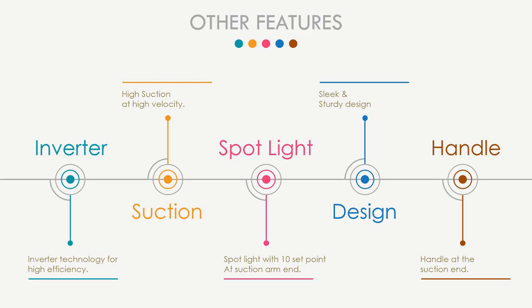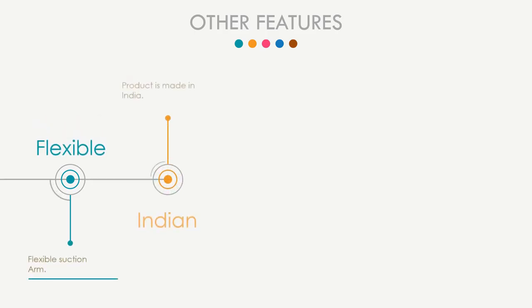EDS-2000 has a built-in power LED spotlight with 10 intensity set points, which is sufficient to perform dental procedures. Knowing that dental procedure rooms are already filled with many machines and instruments, the design team created a sleek yet sturdy machine. It has a handle at the end of the suction arm for ease of use, and the suction arm is highly flexible.